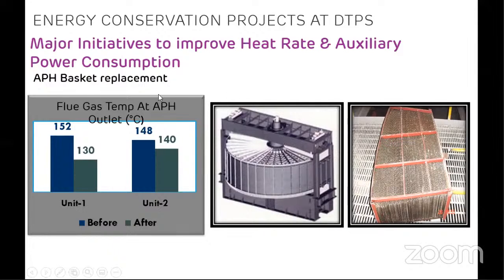So we carried out basket replacement during the last overhauling. The temperature of flue gas at the outlet of the APH was 152 degrees before this overhauling, and after the basket replacement, it changed to 130 degrees Celsius. So we are gaining 20 degrees Celsius in temperature, which will reflect in boiler efficiency.